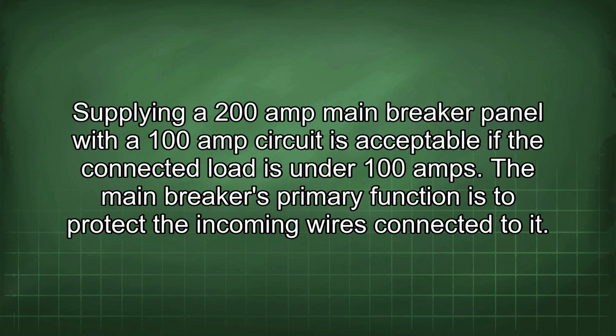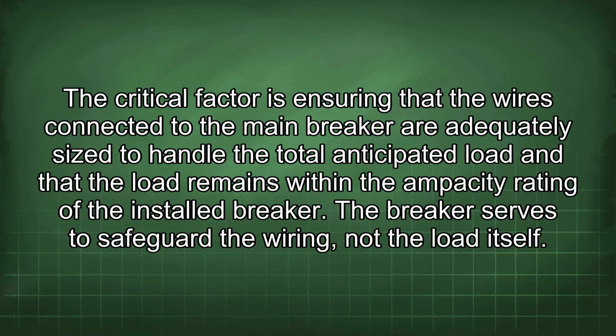Supplying a 200 amp main breaker panel with a 100 amp circuit is acceptable if the connected load is under 100 amps. The main breaker's primary function is to protect the incoming wires connected to it. The critical factor is ensuring that the wires connected to the main breaker are adequately sized to handle the total anticipated load and that the load remains within the ampacity rating of the installed breaker. The breaker serves to safeguard the wiring, not the load itself.